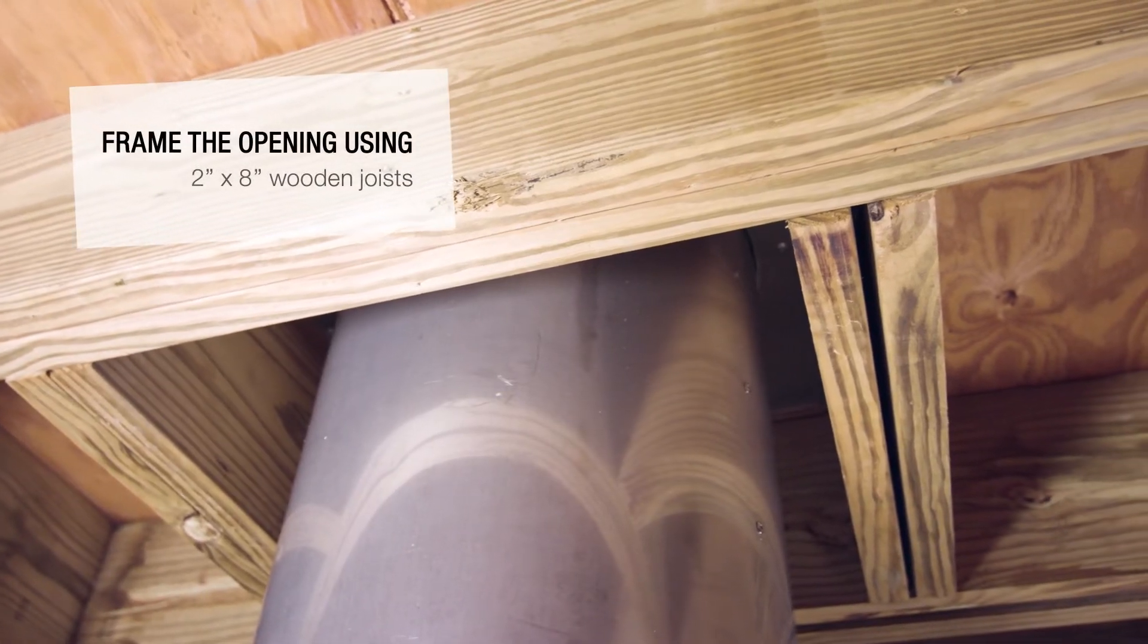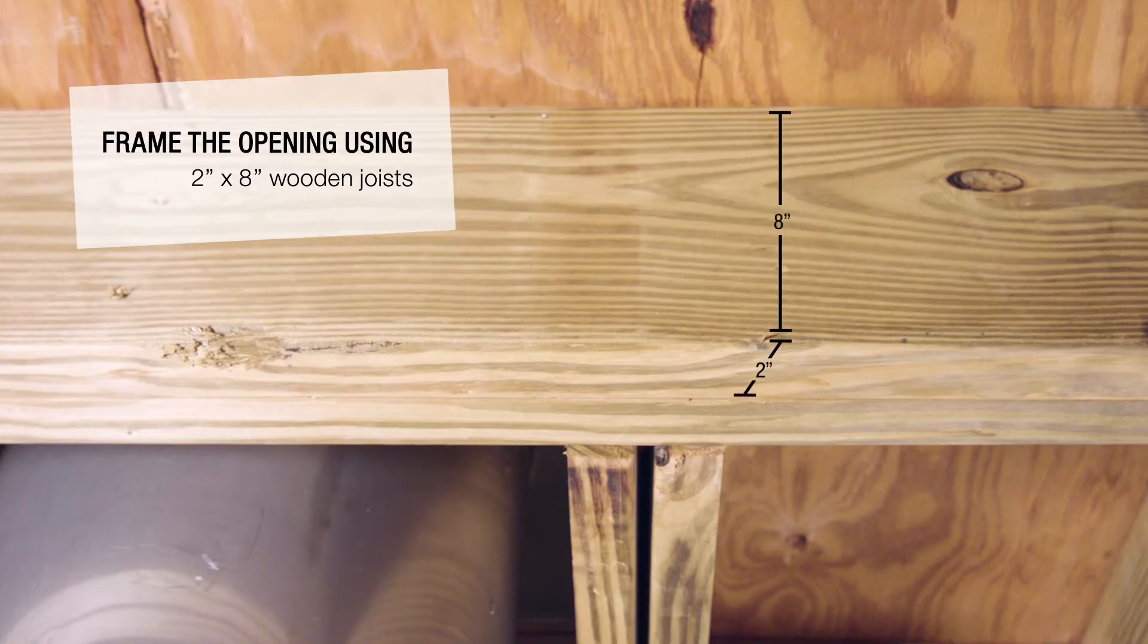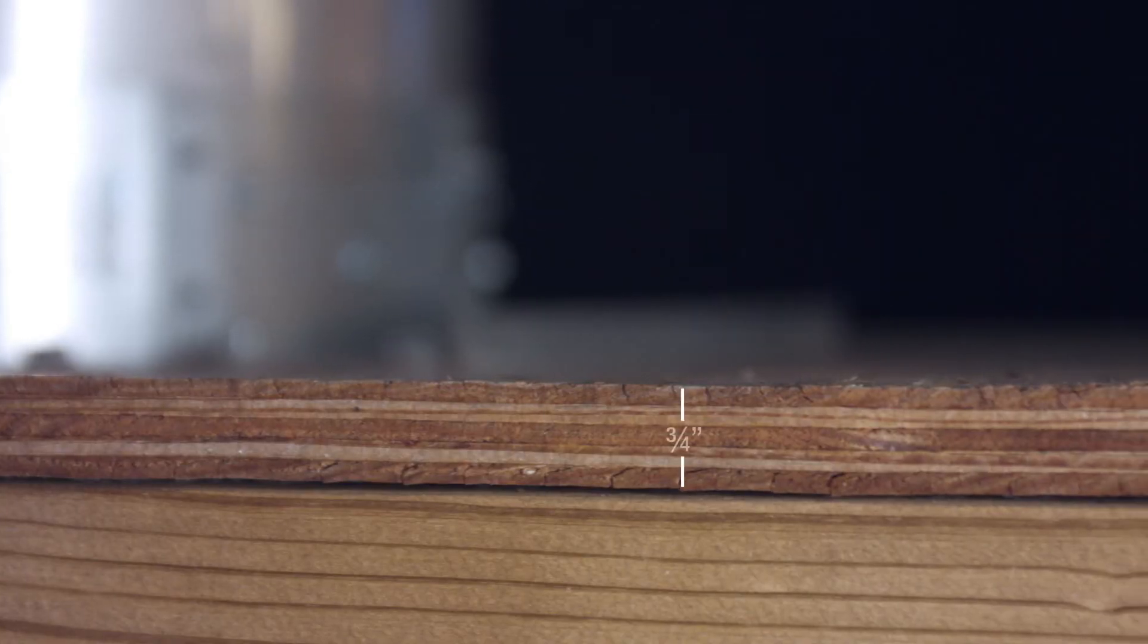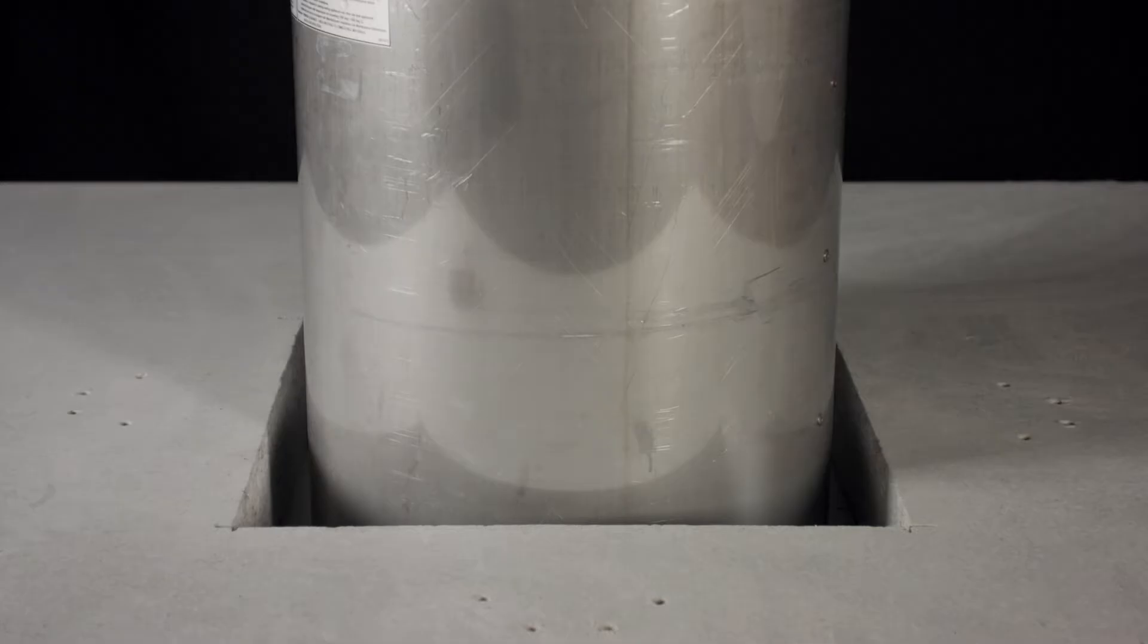The opening must be framed by the general contractor with at least two by eight inch wooden joists covered with three-quarter inch plywood or concrete floor.